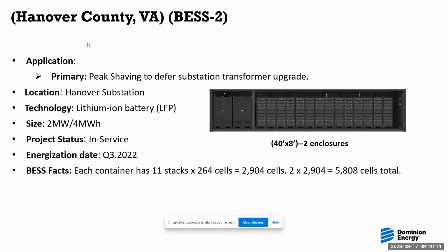You'll always see a peak output with a battery, 2 megawatts, and then a time duration. In this case, I can inject 2 megawatts for 2 hours onto the system—take that 4, divide it by 2, that's where I get it. This project is in service; we energized it Q3 of last year. Some fun facts: it's 2 enclosures, each 40 feet by 8 feet. Each enclosure has 2,904 cells, for a grand total of 5,808 cells. This has a primary application of peak shaving to defer substation transformer upgrades.